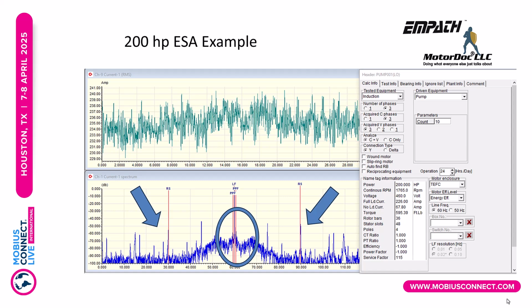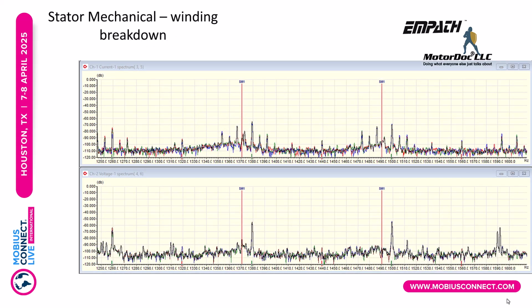A 200 horsepower machine. This is looking at electrical signature analysis. You can see we have all of our nameplate information there. In this case, we're looking at a winding failure. Now what'll happen sometimes is we'll get some drift. So this one has about a 0.1 hertz resolution. If it's off just by a little bit, in reality the peak should be slightly over to the right. On these, it's primarily in current. And then you'll see side bands of that, and that's related to running speed. That turns out to be the actual winding degradation. It's not reflected in voltage, it's only in current. So that means that the winding is in the process of breaking.